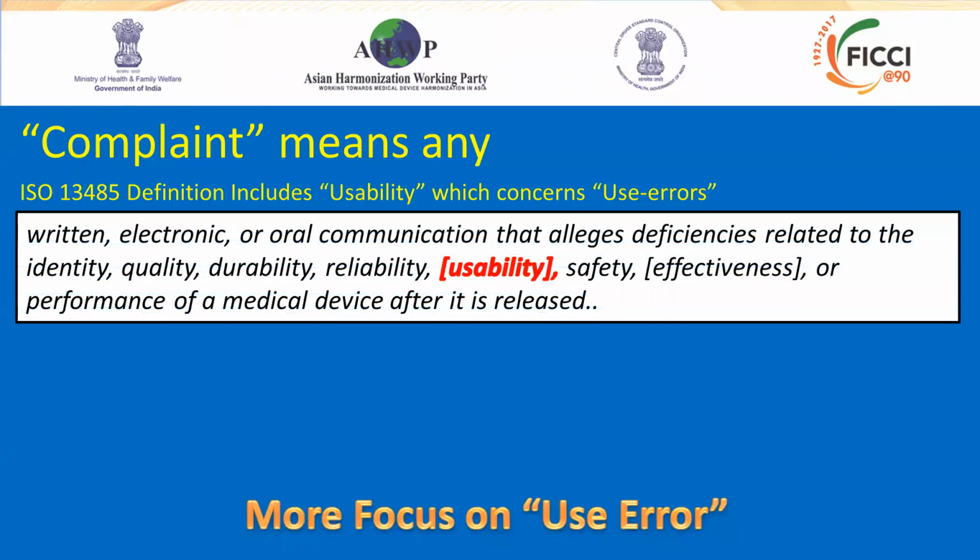So what is a complaint anyway? This is interesting because the FDA definition under Part 820 has basically been copied and pasted into the new 13485:2016 standard with the addition of this word usability. And I think it's a little strange that the FDA hasn't come around and put use errors and usability in their own definition. But here it is in the 13485 standard.